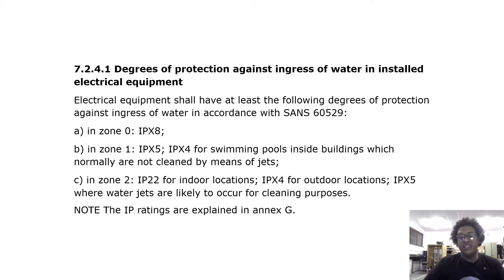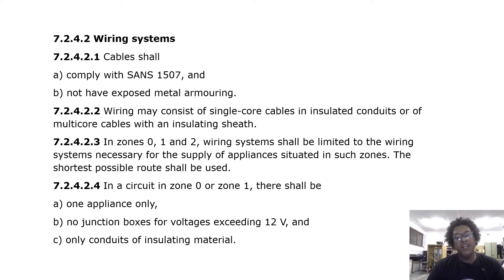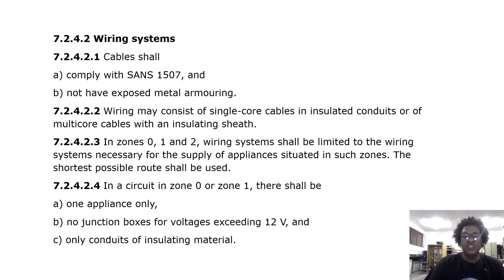Regarding wiring systems: cables shall comply with SANS 1507 and not have exposed metal armour. Wiring may consist of single core cables in insulated conduits or multi-core cables with an insulating sheath. In zones 0, 1 and 2, wiring systems shall be limited to those necessary for the supply of appliances situated inside such zones. The shortest possible route shall be used. In a circuit in zone 0 or zone 1 there shall be one appliance only, no junction boxes for voltages exceeding 12 volts, and only conduits of insulating material.